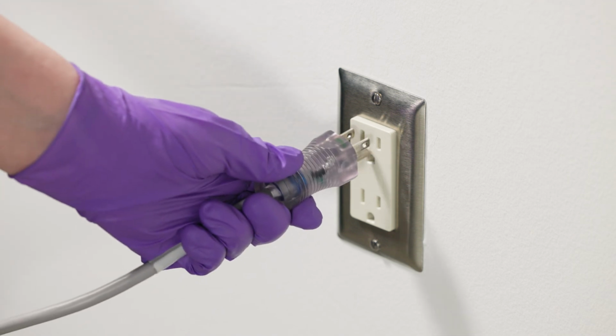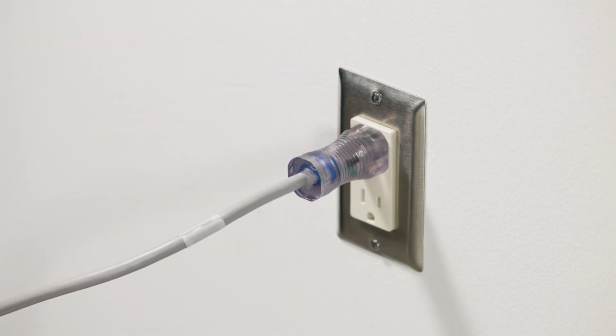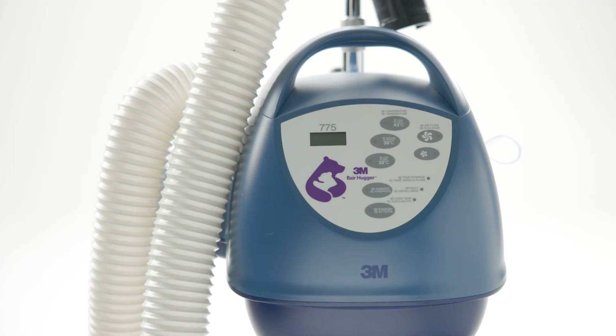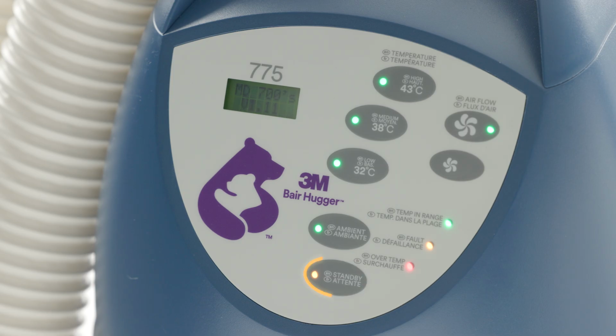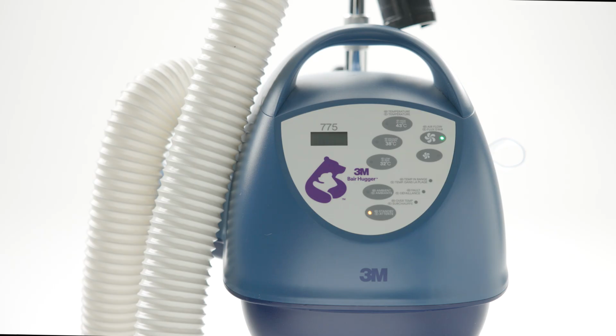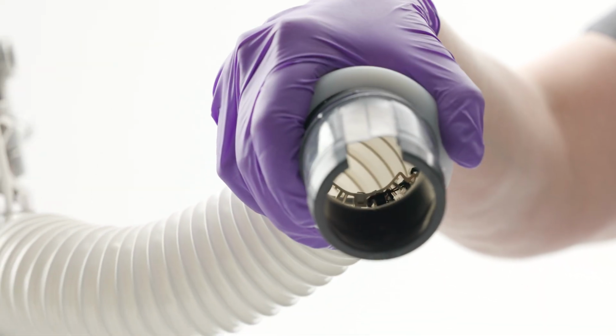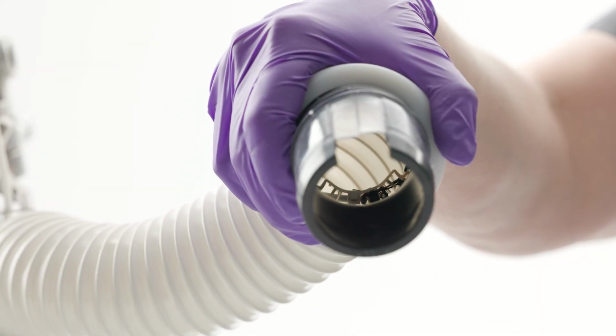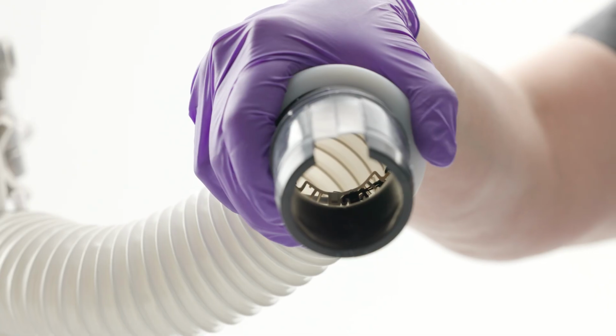Connect the warming unit power cord to a properly grounded power source. An automatic power on reset sequence will start, the standby button will illuminate amber, and the high fan speed will illuminate green to show that the unit has power. The unit has 3 temperature sensors, with 2 of these located at the end of the hose where it connects to the blanket to provide air temperature detection.